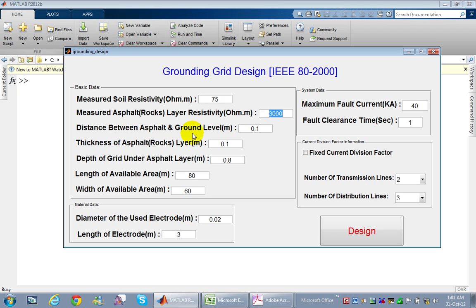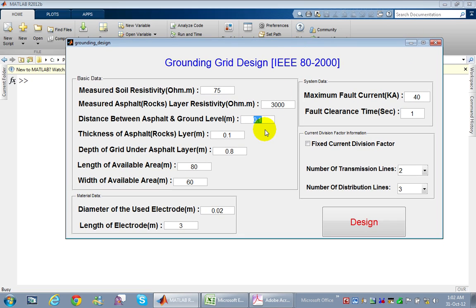The second input is the distance between the asphalt and the ground level. Usually the ground level of the substation is higher than the asphalt level to protect the substation from water in heavy rain areas. Typically a distance of 10 centimeters is used between the substation ground level and the outer asphalt level. Here I assumed 0.1 meters, which is commonly used in Saudi Arabia.